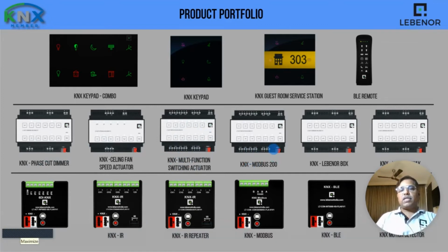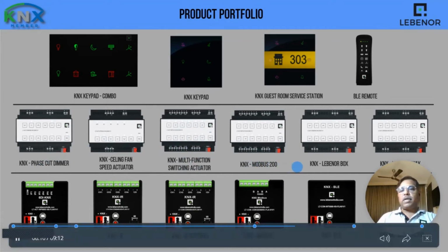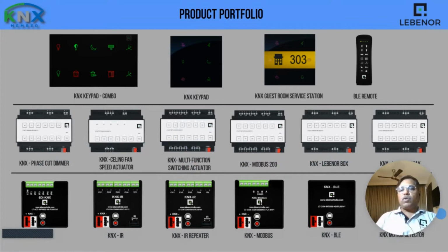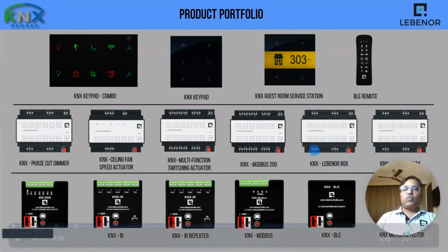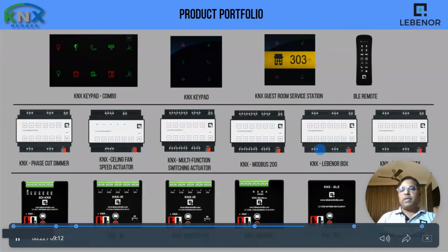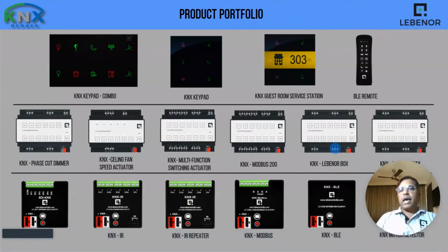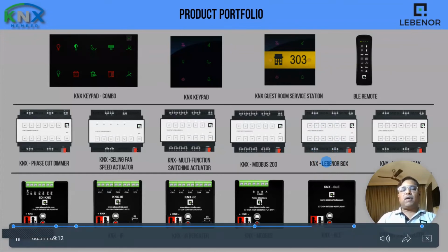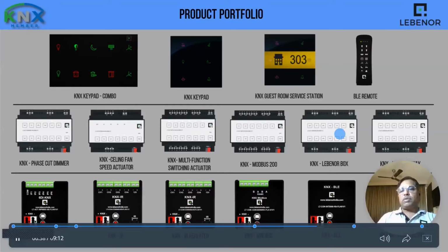This is a KNX to Modbus gateway converter, which can support up to 200 data points. We are also coming up with our own server box called Lebenor box, which will have KNX, Modbus, BACnet, and CAN bus. Various converters and gateways will be developed in future on this particular platform. We have already completed our development of the software, which is currently being shifted onto this particular hardware.